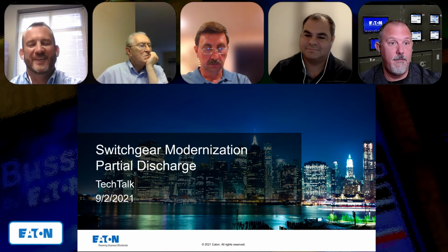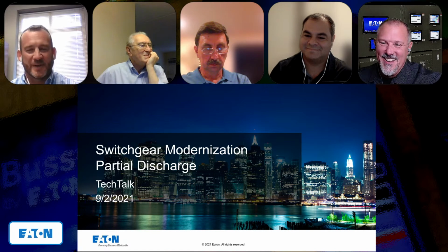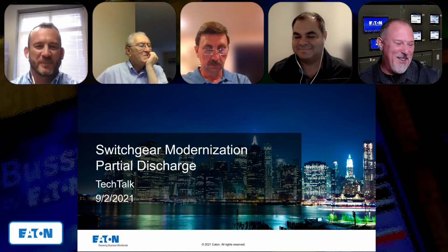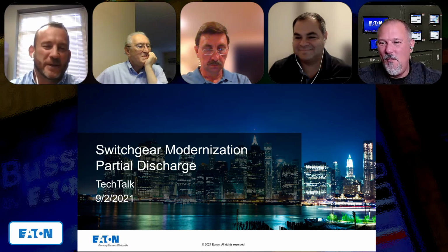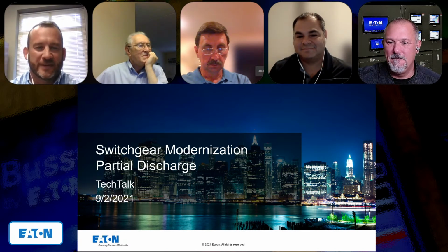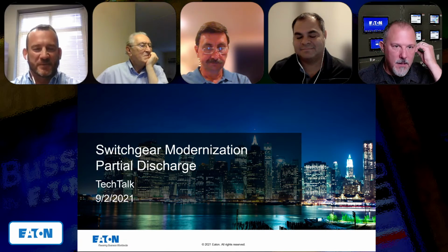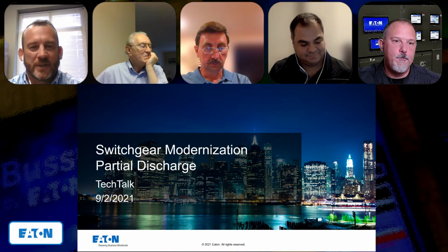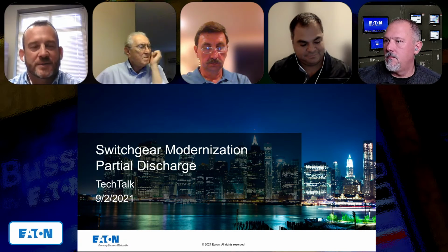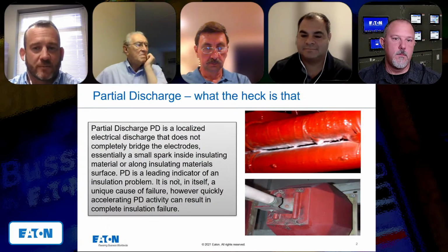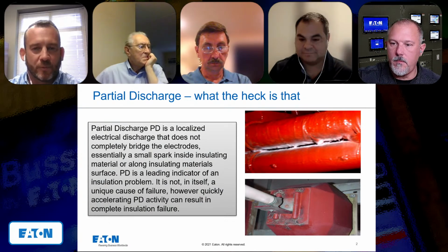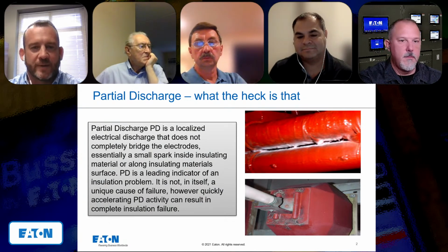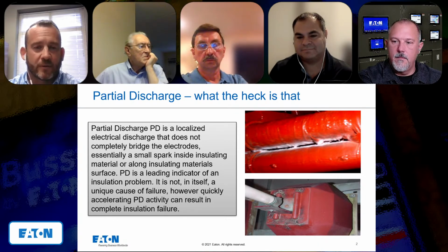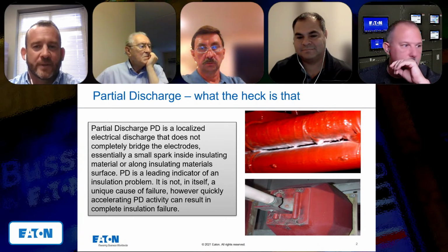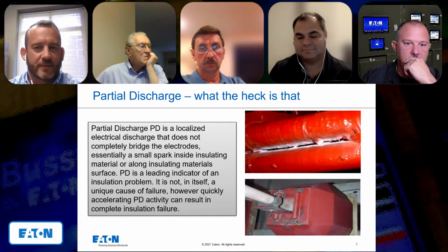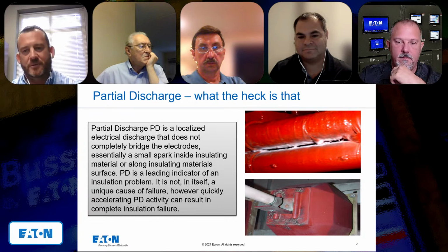If you go fully discharged and it's uncontrolled, then you have real problems, put it that way. But yeah, partial discharge - I'll kick it off. I'm not the expert here, but I'll spew my knowledge on partial discharge. It's a localized small discharge of electricity, right? It doesn't completely bridge the electrodes, meaning it doesn't go phase to phase - not a complete phase-to-phase failure or phase-to-ground fault. It's small little sparks inside the insulating material, and you can see that in the pictures right there.